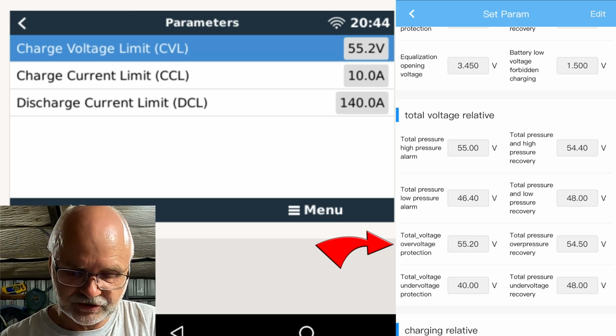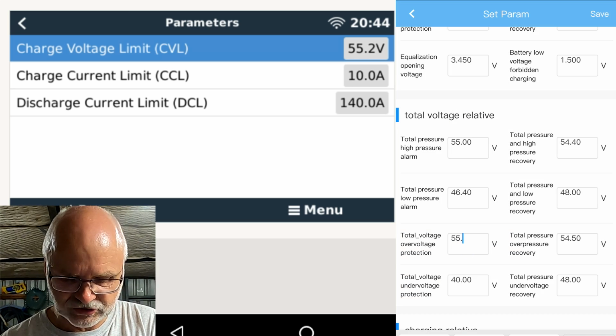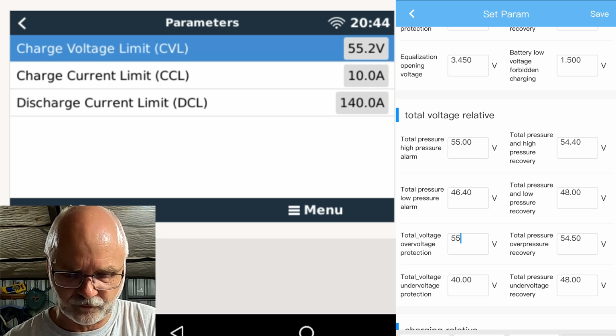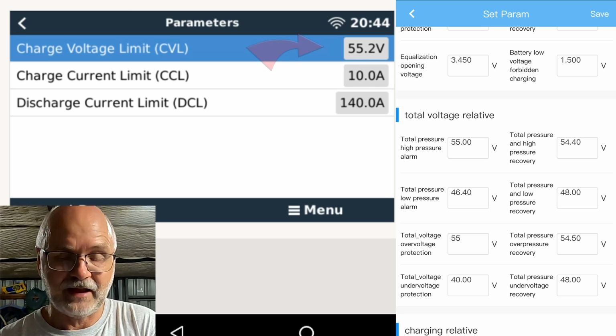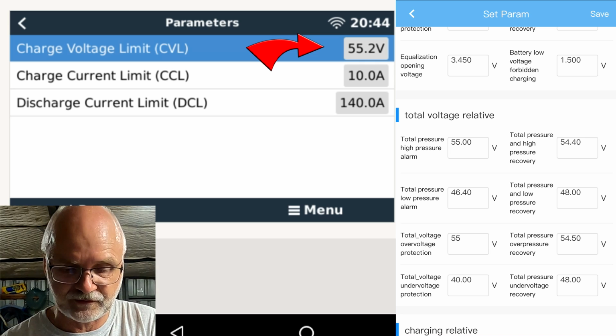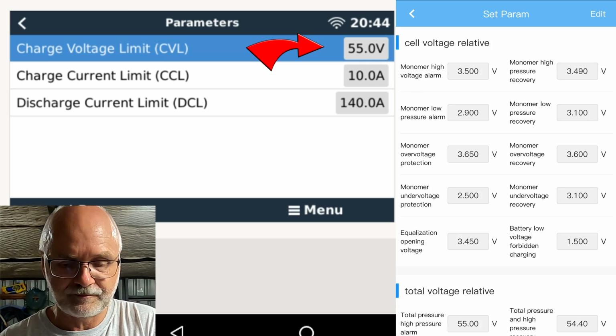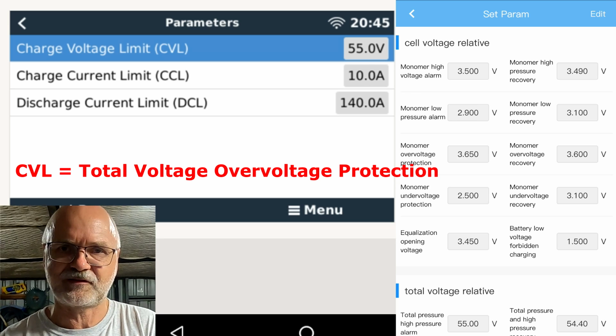So if we want to change this, we click on Edit, put in the password, and then change the value to, say, 55 volts. Save this, and you watch the parameters in the Victron system. Once I click Save, they change to 55 volts. So this is how you control the maximum charge voltage you have in your system then.